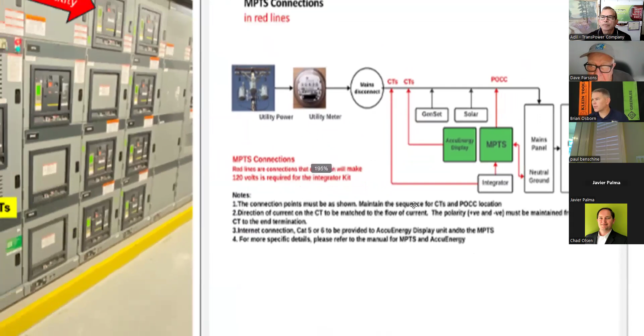So they had this, and this shows the transformers outside, the utility meter, the main disconnect switch. I think this is the main disconnect switch. And then you see the CTs, two sets of CTs. And then you have a point of common coupling for the MPTS. The green is the accu energy meter and the MPTS power management. And this is the power to the MPTS. Do you see the CTs? How they are placed? Yeah, I do see how the CTs are placed. And of course it is on the line side or source side of the point of common coupling.